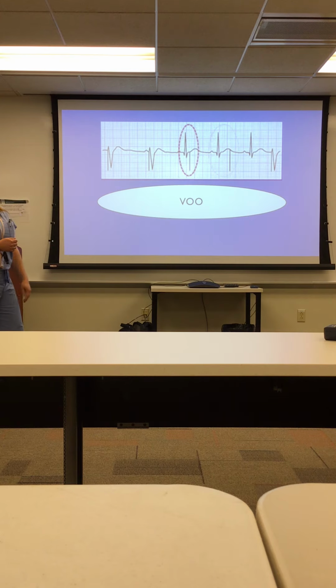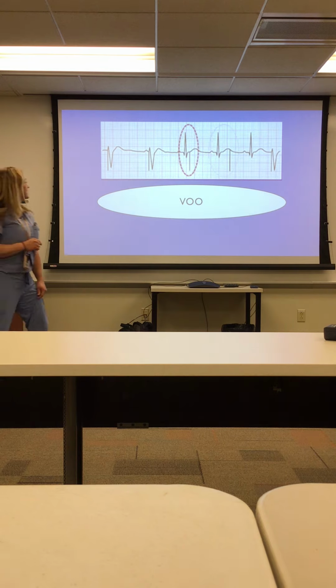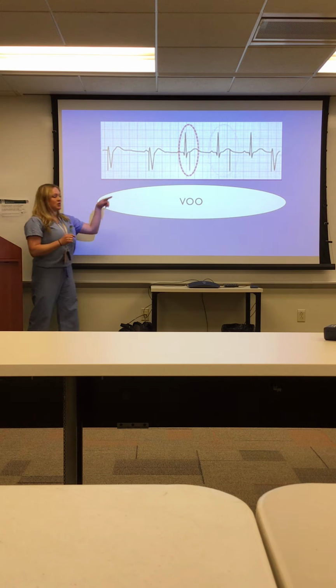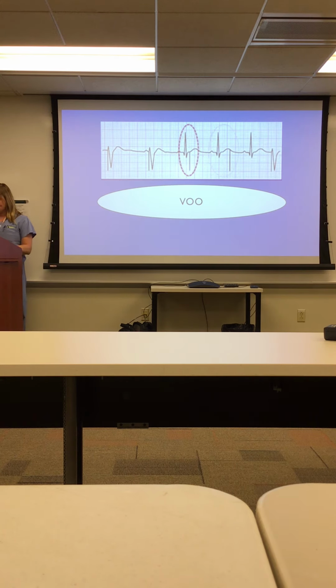Even with it not sensing, it'll still march out. Yep. So say they're coming in on their own around 60s and 70s, I would make sure to program them at least 80 or 90, just to make sure you're 10 above that. You want to be in the driver's seat when you're in an asynchronous mode. That's the biggest thing I would say to remember, so you don't run into that scenario.